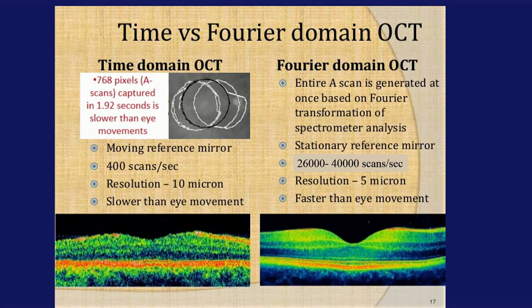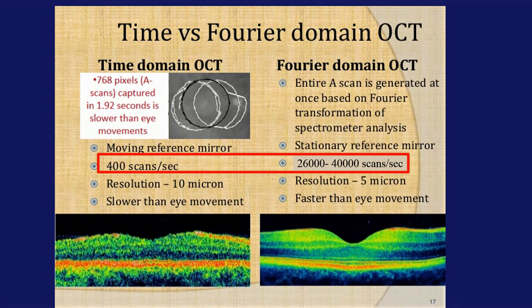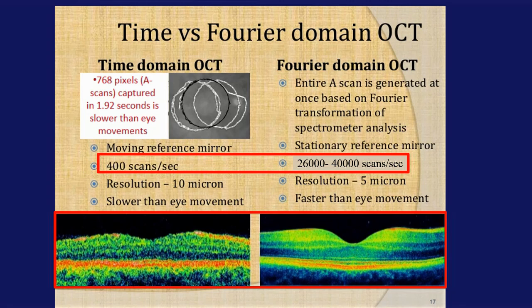Time domain OCT is a slow process because it depends on the mechanical movement of a mirror, allowing eye movements to be captured as artifact. It achieves only about 400 scans per second. Spectral domain OCT, using the Fourier transform, achieves 26,000 to 40,000 scans per second — far faster than eye movement — producing much more stable images. Resolution is also better at 5 microns compared to 10 microns for time domain. This speed also enables OCT angiography, which will be discussed in another presentation.